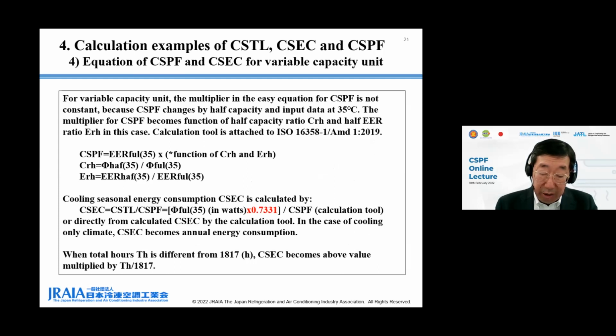This page shows the equation of CSPF for variable capacity unit, with a similar style to the easy equation for fixed capacity unit. For variable capacity unit, the multiplier in the equation is not constant and becomes a function of half capacity ratio CRH and half EER ratio ERH. CRH is 35 degrees C half capacity divided by 35 degrees C full capacity, and ERH is 35 degrees C half EER divided by 35 degrees C full EER.